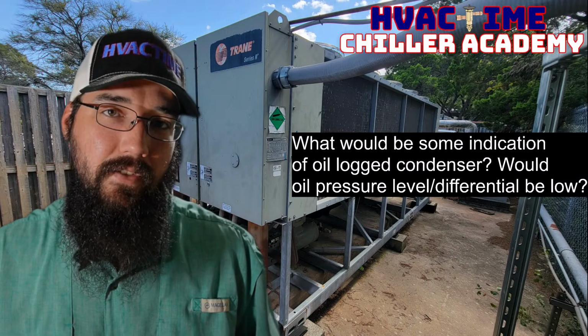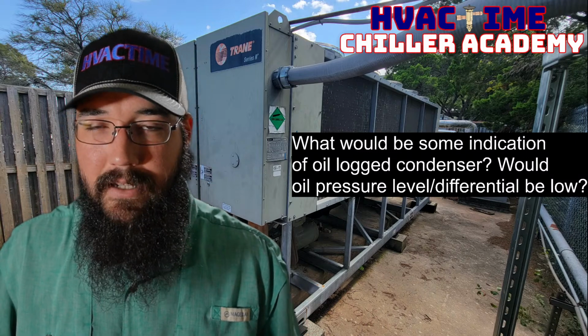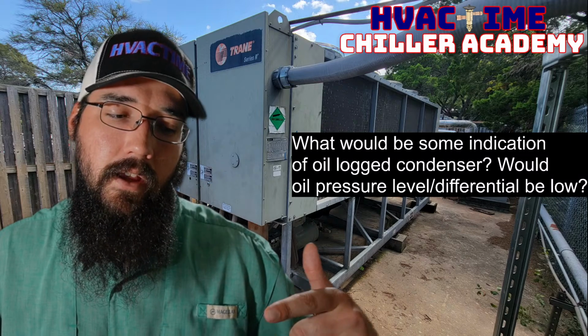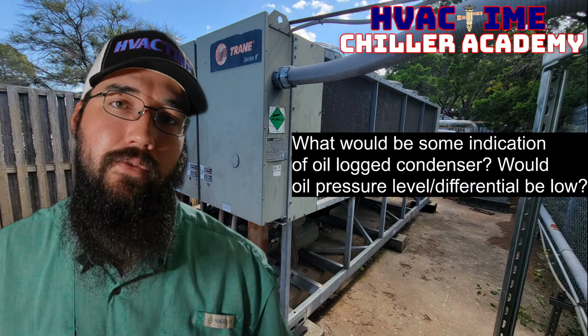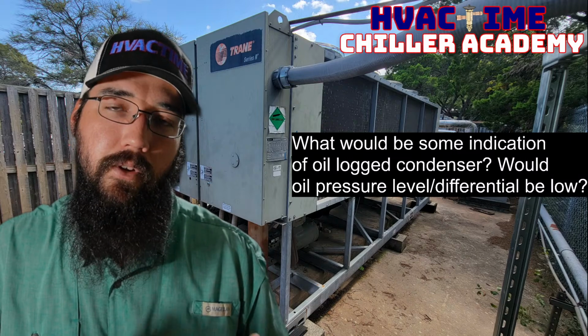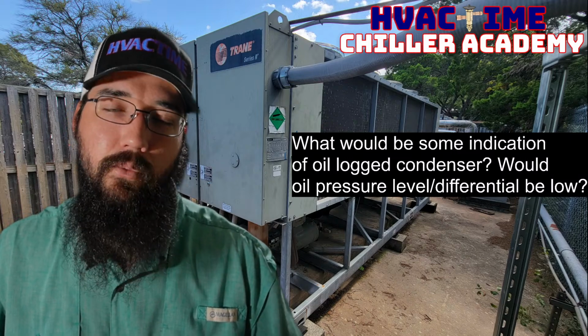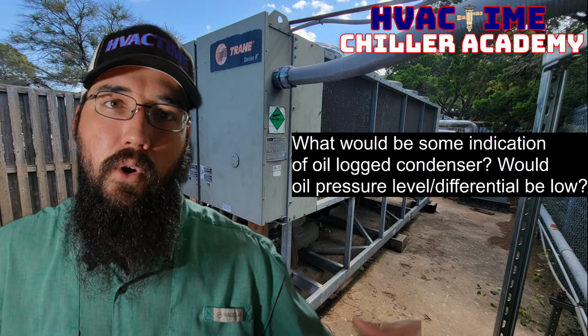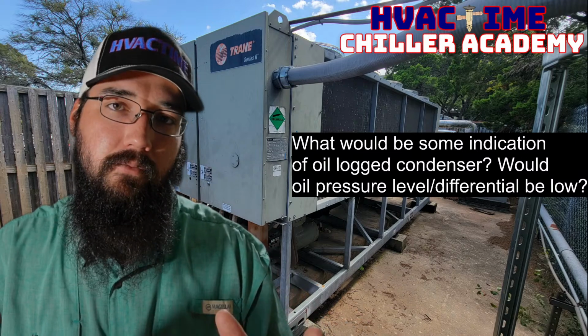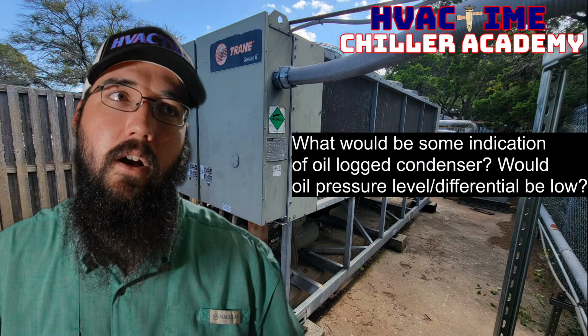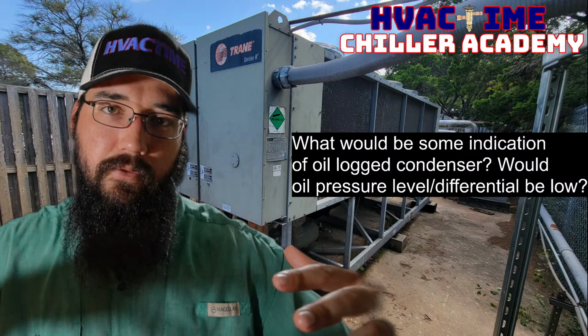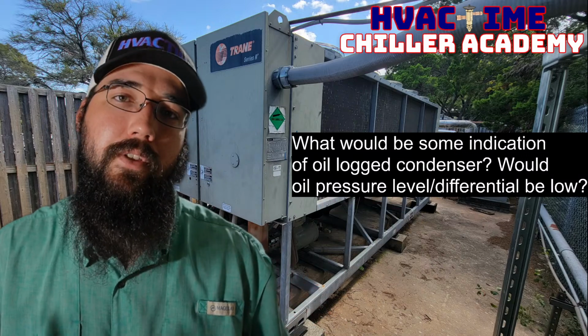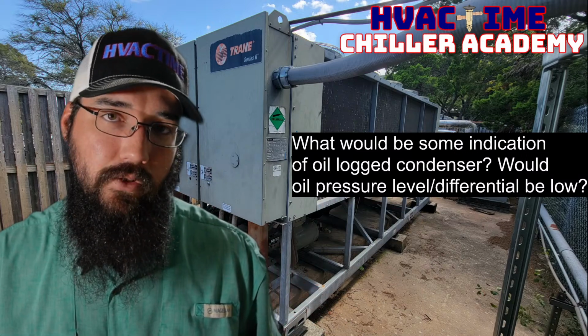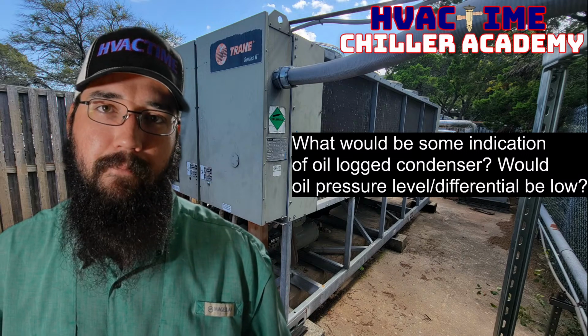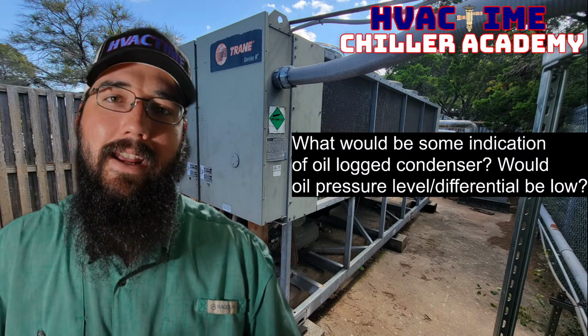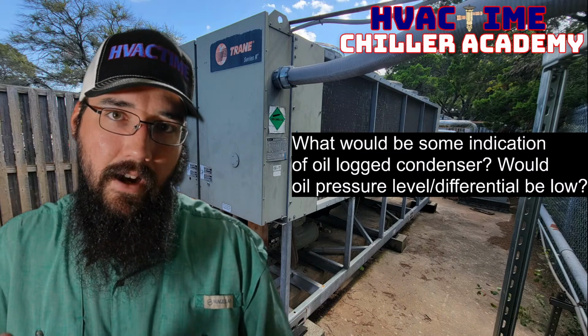If we have a DX evaporator or a braze plate, it's typically not so severe because we usually have a much higher velocity through the heat exchanger. With falling film and flooded, we don't have a lot of focused velocity that can carry that oil up the heat exchanger with the vapor and out. But with a DX, where the refrigerant is inside the tubes, or with a braze plate, we can maintain a lot higher focused velocity.